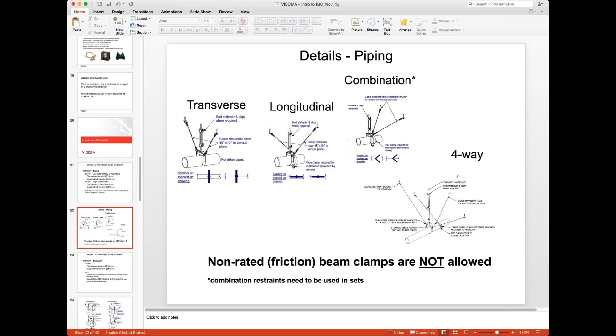Now, it's important to know that Sammy mentioned the cable and the rigid bracing. When it's cable, as we know, cables can only take tension. You can't push on a rope. So a transverse would require two cables. You can also design this restraint for a rigid brace that only technically can be in one direction off of the pipe, but it has to be designed for the compression load. So it'll take the tension load relatively easily, regardless of the length. But once that brace is too long, you have to check the buckling of it. So when you go for rigid bracing, you can put one, but depending on the load, you do got to check for compression buckling.